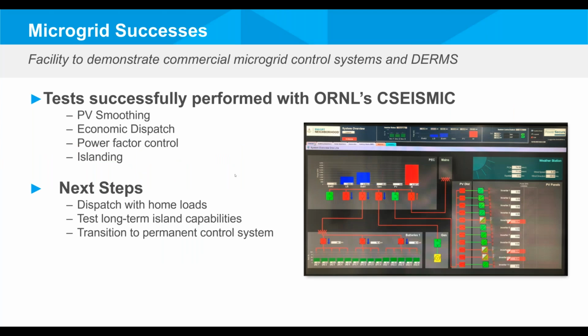So overall, I've talked about the microgrid, what went into designing the microgrid, the smart homes, and customer insight. For the different use cases on the microgrid, we've done PV smoothing to help smooth the ramp up and ramp down and reduce the impact on the power factor. We've done economic dispatch using arbitrary cost to try to optimize the dispatch of the microgrid. We've talked about power factor control and also about different cases of islanding and how the microgrid was able to carry the smart homes in them, which also includes the multi-source grid forming.